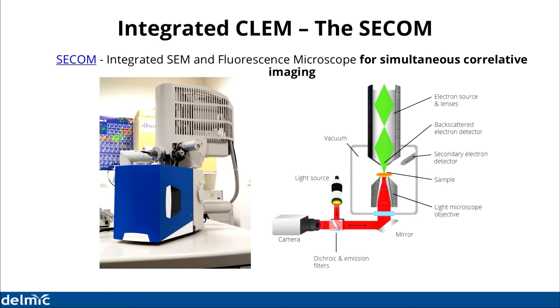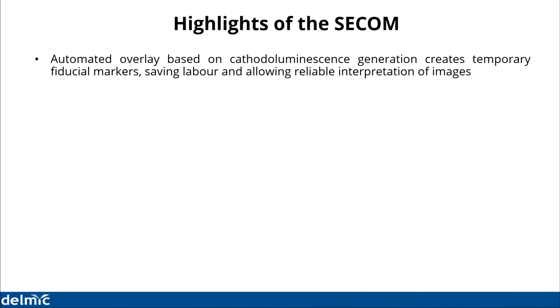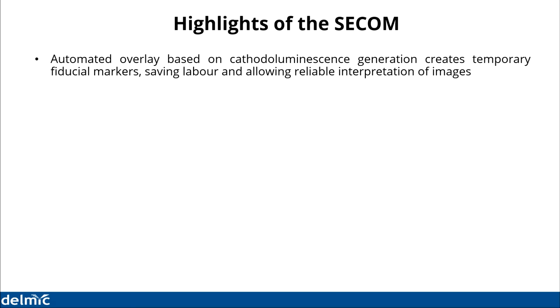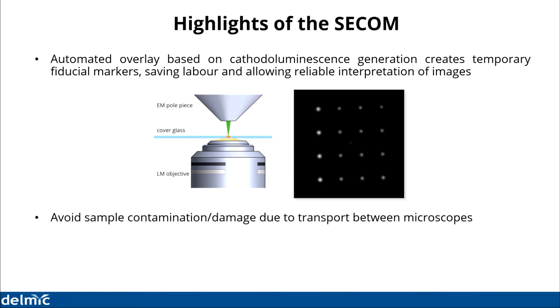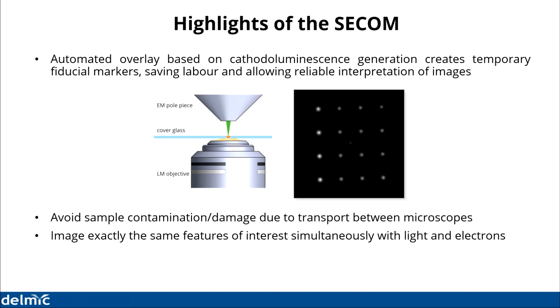Why is integrated CLEM performed this way? The main highlights of the SECOM are that it's possible to have an automated overlay between the electron image and the optical image. One of the main challenges in conventional CLEM is that performing a manual overlay between the two images is very laborious, time-consuming, and prone to error. In the SECOM, the automated overlay is performed based on cathodoluminescence generated when the electron beam strikes the sample, creating temporary fiducial markers used to perform the overlay in an automated manner. Having one system do both imaging schemes avoids sample damage or contamination, because it avoids transportation between microscopes altogether. You can be sure you're imaging exactly the same features or region of interest in both systems, because it's done simultaneously.